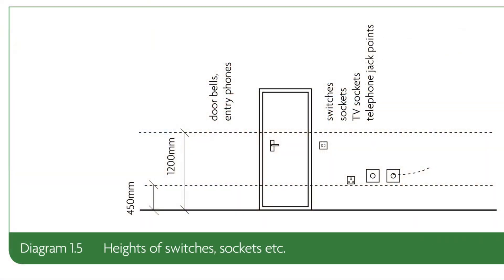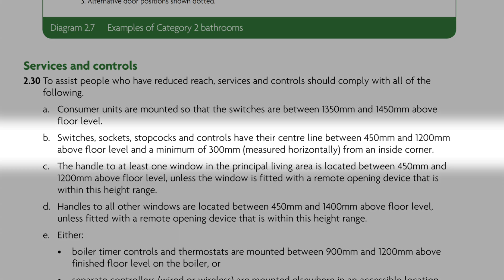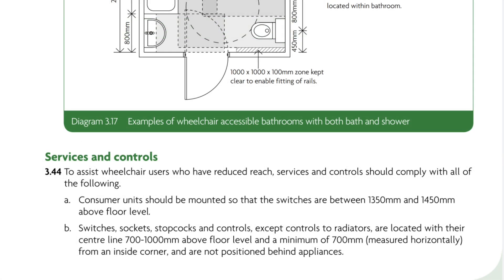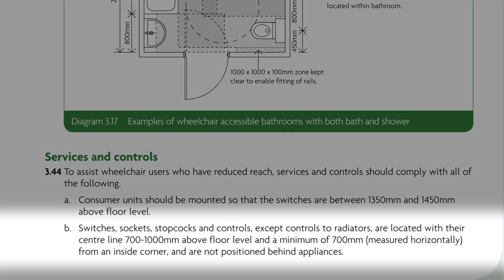For category one, switches and sockets serving habitable rooms throughout the dwelling have their centre line 450 to 1200mm above floor level. Category two dwellings should have switches and sockets with their centre line 450 to 1200mm above floor level, with the additional requirement that they are also at least 300 millimetres horizontally from an inside corner.